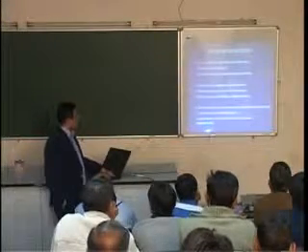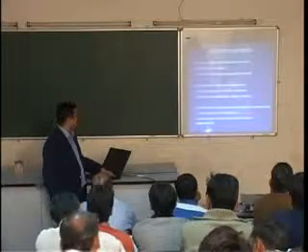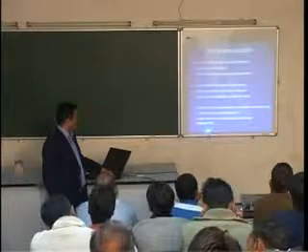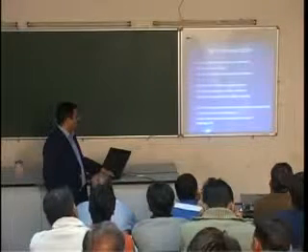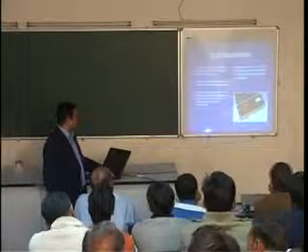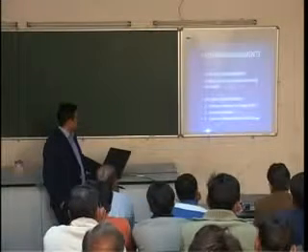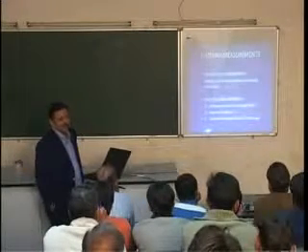So there are different ways of carrying out the vector error correction technique. I will not go into the details of that, but I will just tell you that it depends on whether you want to do a one port calibration, then you need to measure only 3 systematic error terms and remove them. And if you want a full 2 port, then 12 measurements are required, and there are different kits available to remove these errors. And once these errors are removed, this is all one can do to remove the error of the total system.